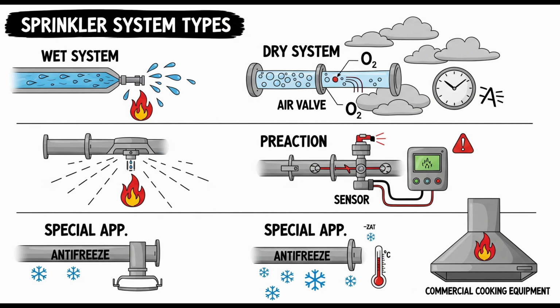Exactly. So, NFPA 13 requires protection against this accumulation, using either an automatic high water level signaling device, basically an alarm, or an automatic drain to get rid of the water. Okay. Addressing a specific risk for certain valve designs. Let's talk about the air pressure itself and the supply system for dry pipes. The source clarifies air can include nitrogen or other approved gas. Correct. Whatever gas is used, the pressure must be maintained continuously, year-round. All the time. The supply must come from a reliable source that's available at all times and has enough capacity to restore normal system pressure within 30 minutes after activation or testing.